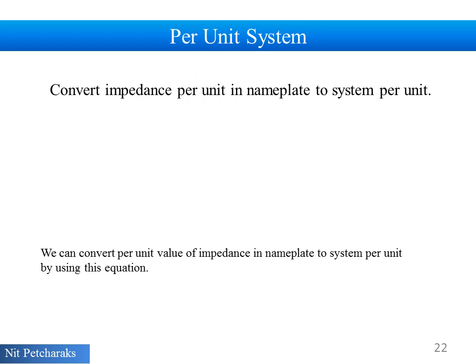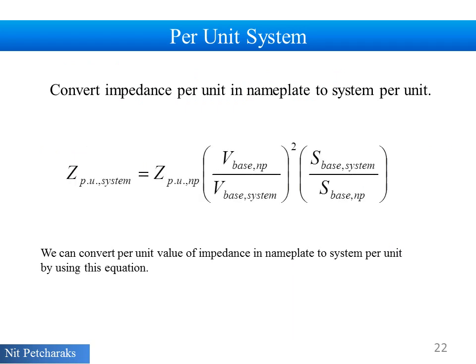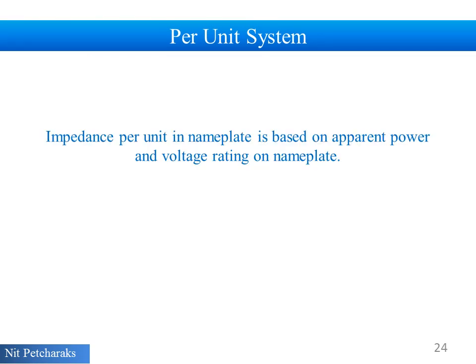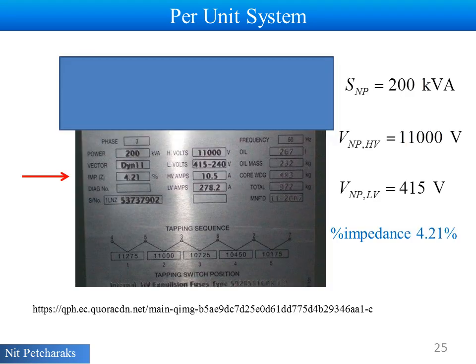We can convert per unit value of impedance in nameplate to system per unit by using this equation. This is example of nameplate of transformer rating. Per unit value of impedance in nameplate is based on apparent power and voltage rating on nameplate. The percentage value of impedance is 4.21.